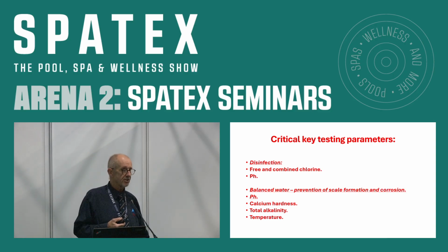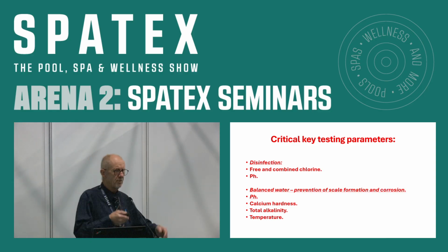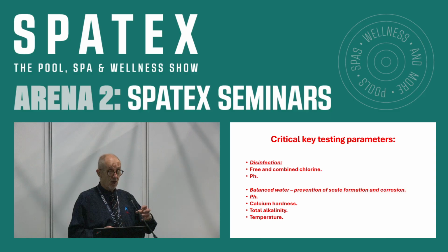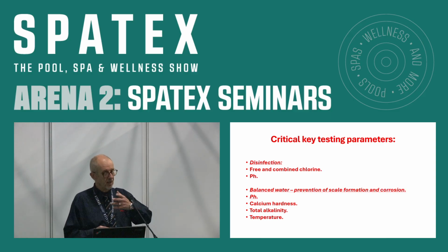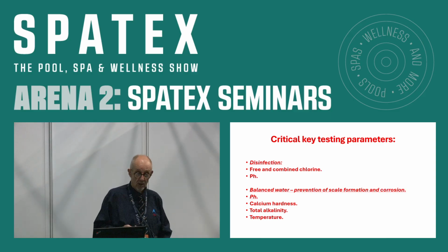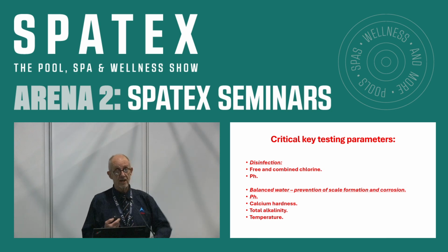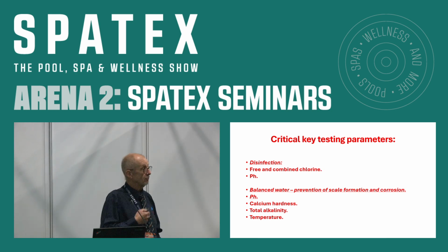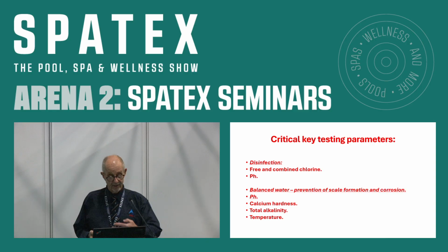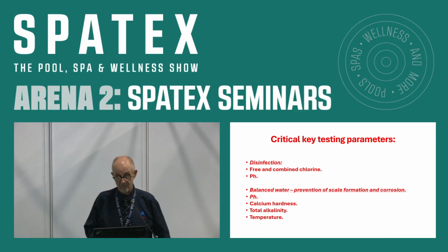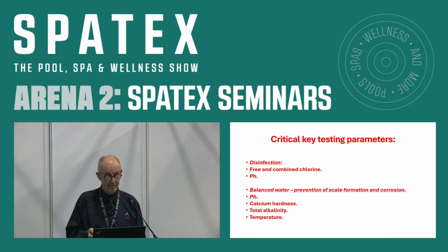Some people miss this. They think, well, if we do the chlorine and the pH, or the bromine or whatever. But it's critical, balanced water. If you haven't got balanced water, this was the case down in this hot tub scenario where they had caking up because they didn't control the water. They didn't control the incoming water and they didn't control the actual hot tub water. So you've guessed it, every 9 months they'd have to replace a pump because the hardness was creating major problems, and therefore you're providing a site for biofilms to grow.